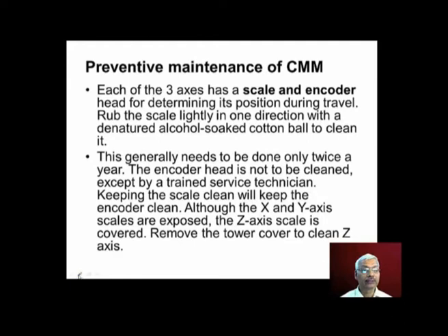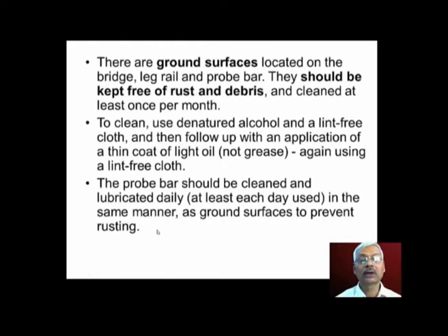So keeping the scale clean will keep the encoder clean. Although the X and Y axis scales are exposed, the Z axis scale is covered. So we should remove the tower cover to clean the Z axis. There are ground surfaces located on the bridge, leg rail and probe bar.